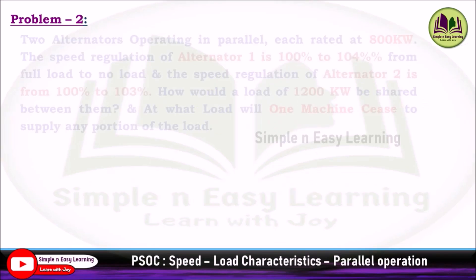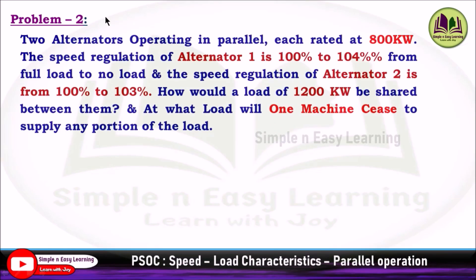Speed load characteristics of two alternators operating in parallel — speed load characteristics, solved problem 2. Two alternators operating in parallel, each rated at 800 kilowatt. The speed regulation of alternator 1 is 100% to 104% from full load to no load, and the speed regulation of alternator 2 is from 100% to 103%. How would a load of 1200 kilowatt be shared between them? Second: at what load will one machine cease to supply any portion of the load?